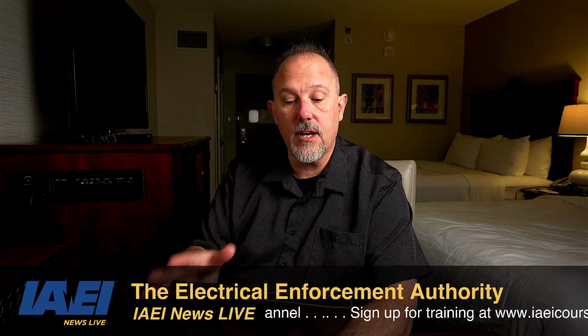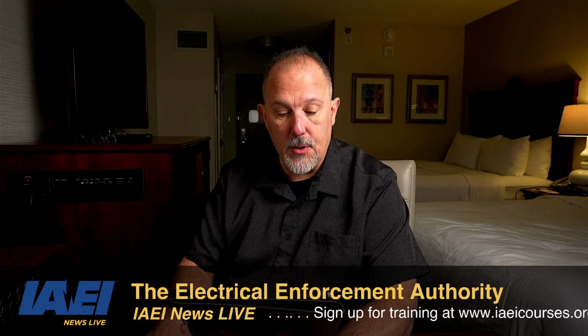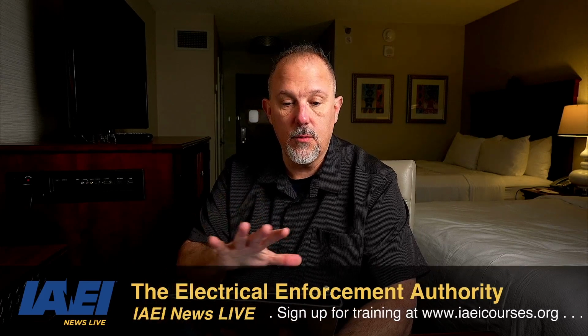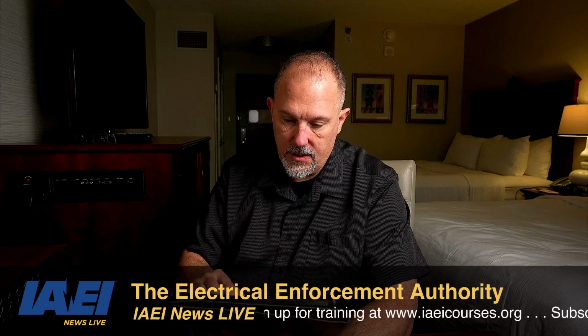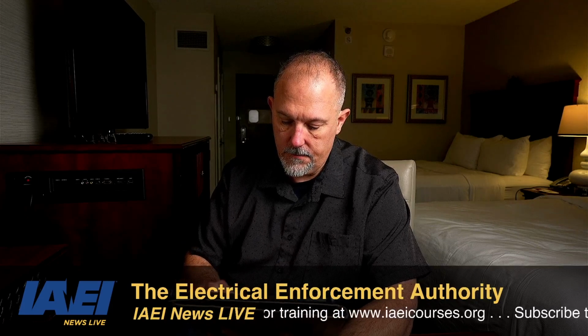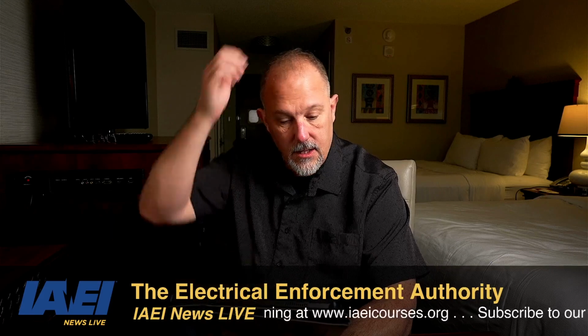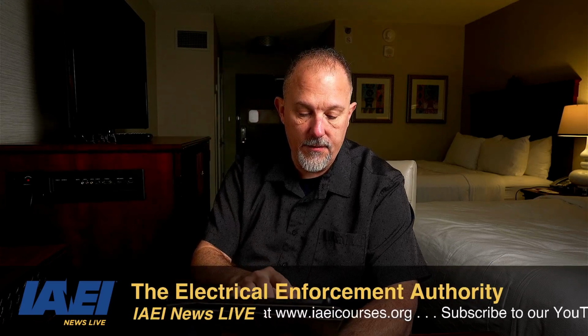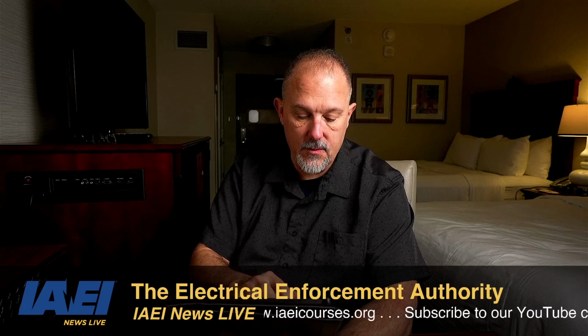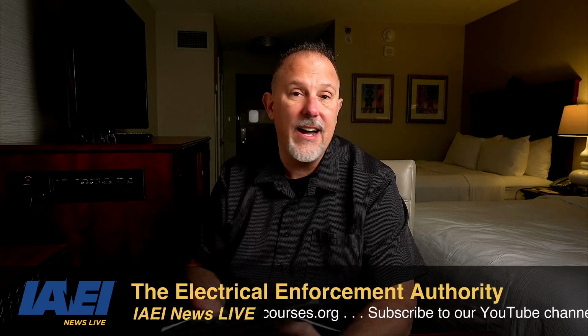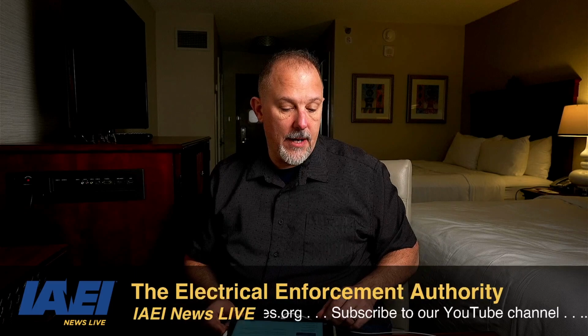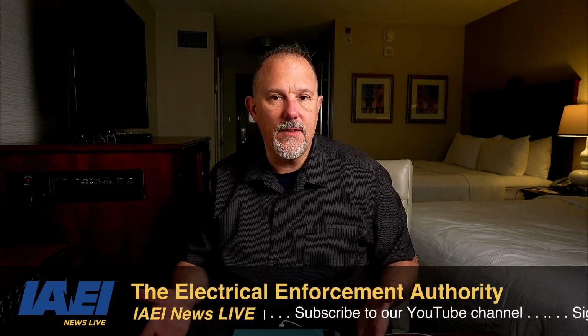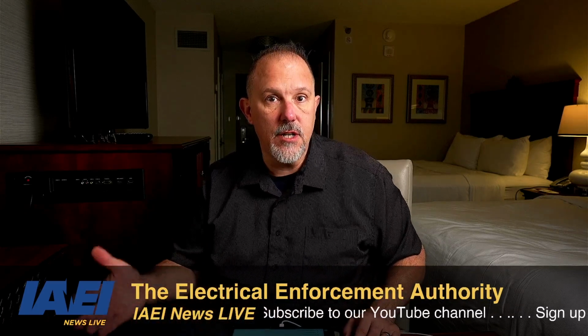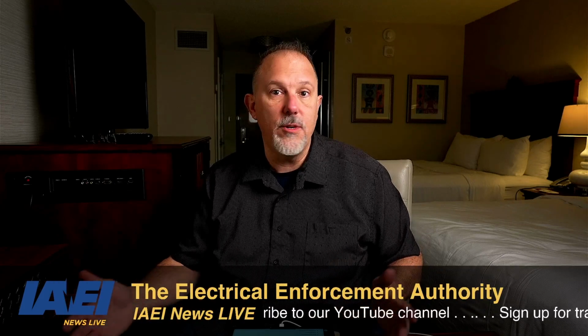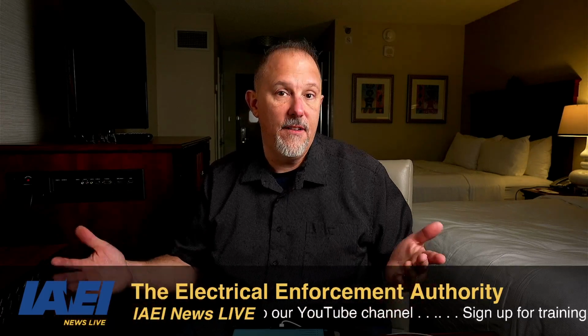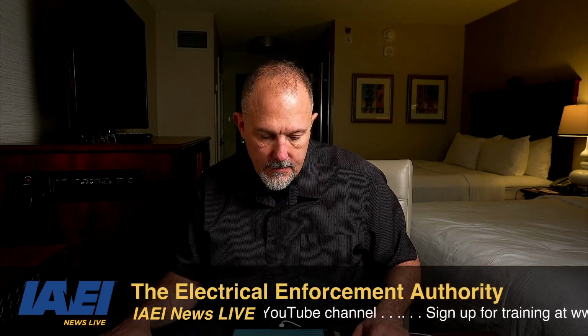445.20. And then here they talk about floating neutral generators and bonded neutral generators. So you have two requirements there. All right. Agree? I guess that is all of the requirements. So there's only 1, 2, 3, 4, 5, 6, 7, 8, 9, 10, 11, 12, 13 sections in 445 for protection of that generator. And we know what the requirements are. We know we have to have a disconnect. We know that those are feeder conductors on the output of that generator, and we just have to protect those based upon feeder protection.